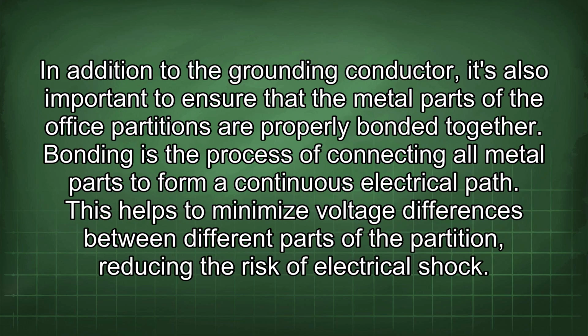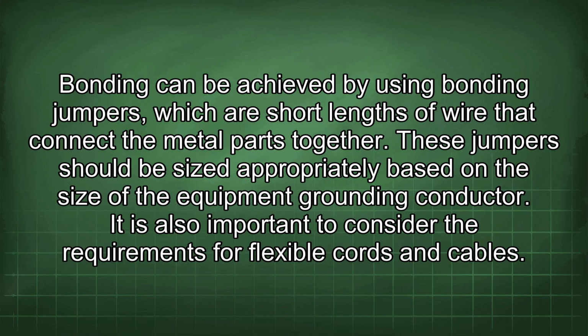In addition to the grounding conductor, it's also important to ensure that the metal parts of the office partitions are properly bonded together. Bonding is the process of connecting all metal parts to form a continuous electrical path. This helps to minimize voltage differences between different parts of the partition, reducing the risk of electrical shock. Bonding can be achieved by using bonding jumpers, which are short lengths of wire that connect the metal parts together. These jumpers should be sized appropriately based on the size of the equipment grounding conductor.